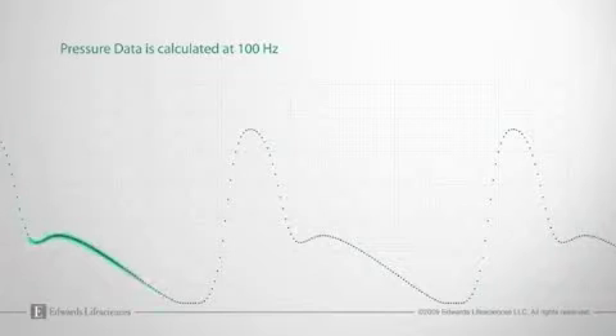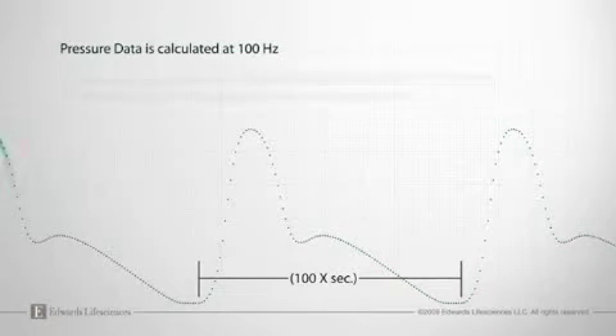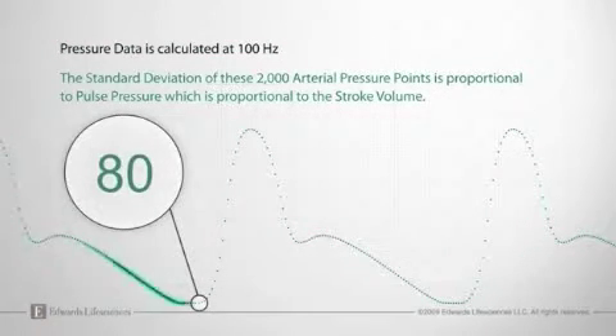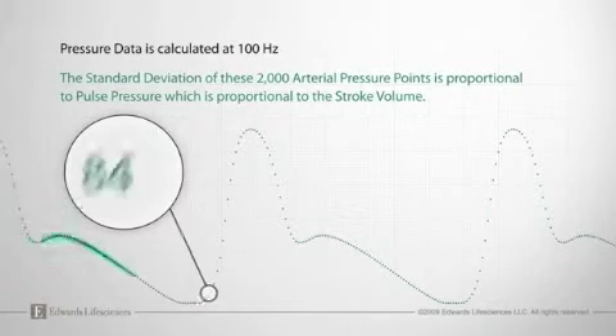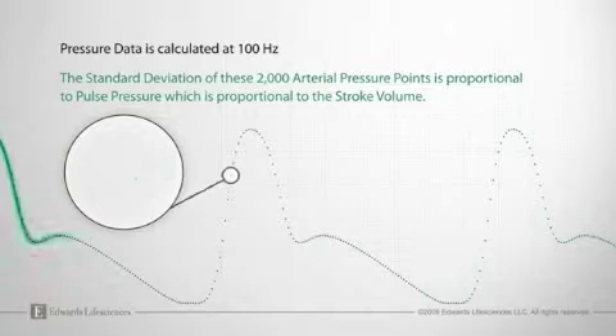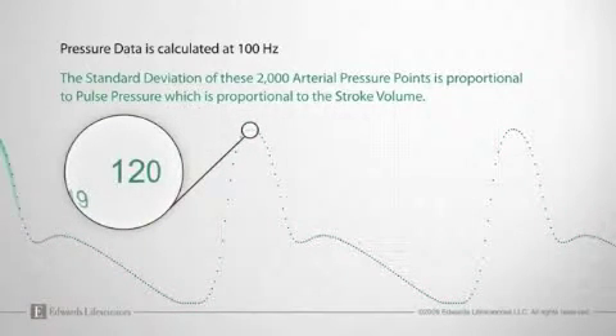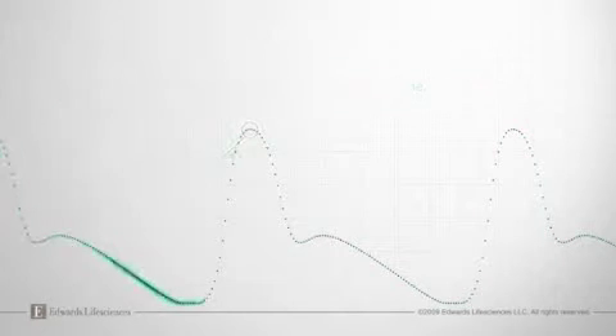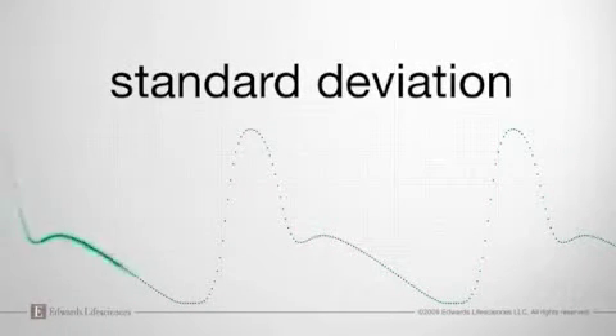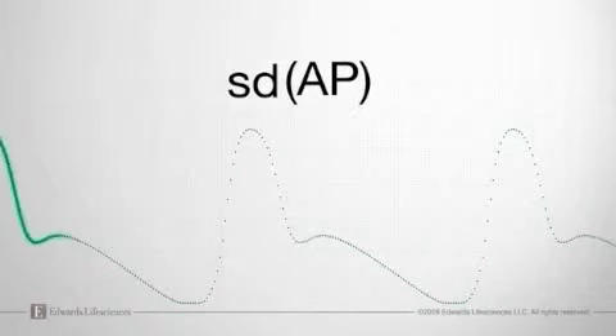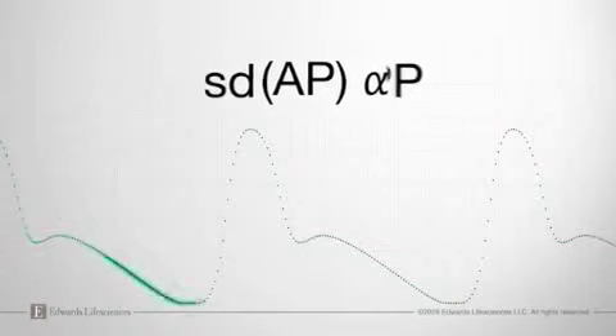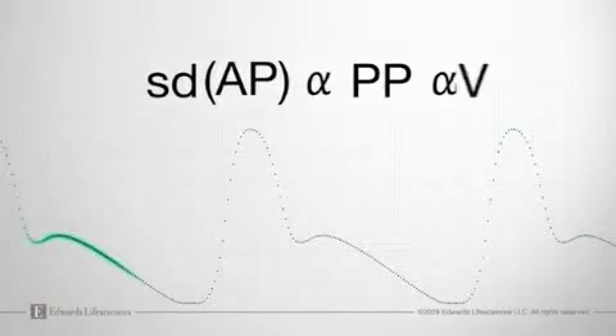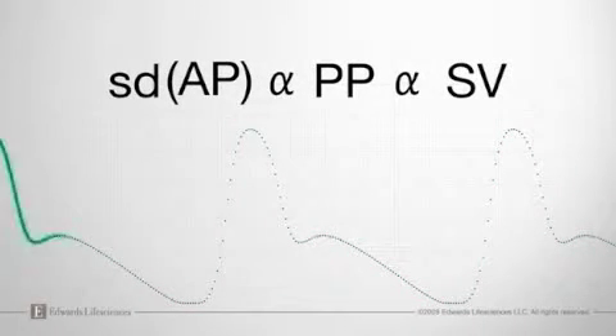Using the waveform generated by the arterial pressure signal, FloTrac samples the arterial pressure at 100 Hz. Each sample is a pressure data point measured in millimeters of mercury. This data is analyzed and updated every 20 seconds, utilizing the 2,000 data points, 20 seconds by 100 Hz, collected. The algorithm then performs a standard deviation calculation on these arterial pressure points. The standard deviation, or quantitative assessment, of these data points is proportional to pulse pressure, which is in turn proportional to the stroke volume. The result is a robust measure of stroke volume because it looks at the entire arterial waveform.